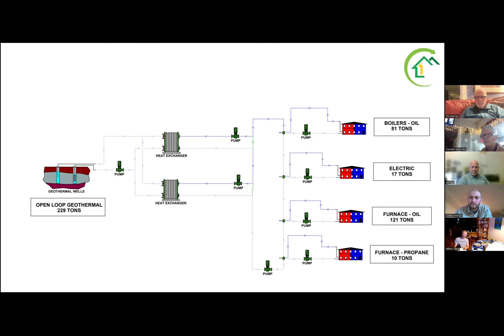Do you have any estimate on what the COP of the system will be? That's a great question — Jay or Justin, do you have an answer for that? The average COP on energy networks is a minimum of 3. If there's good load diversity, it can go above 7. I don't think there's good specifics on the load yet, but those were the numbers I was going to say. Have you calculated it or estimated what it would be in particular for this community?